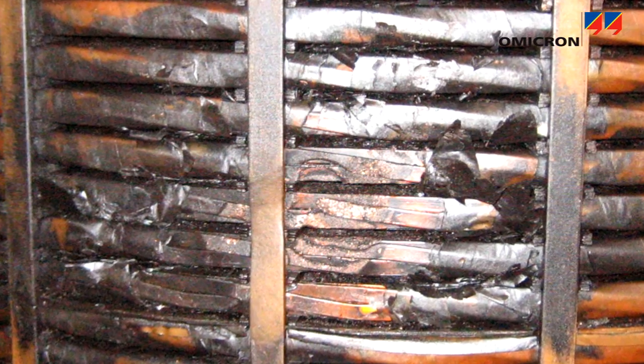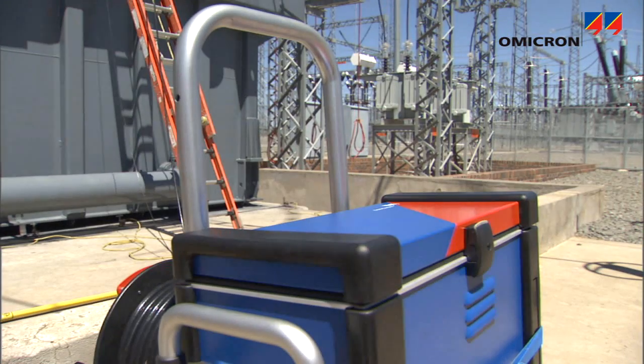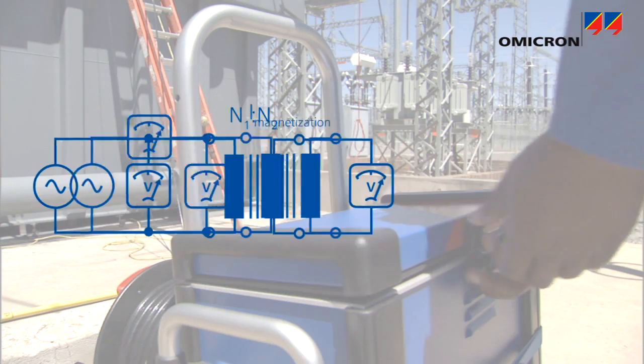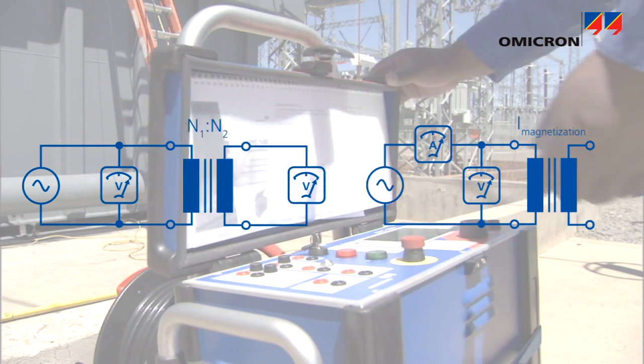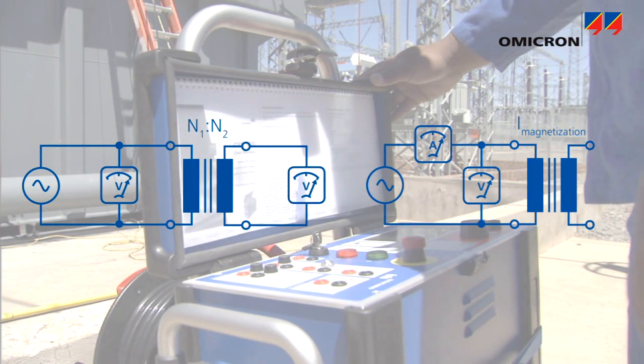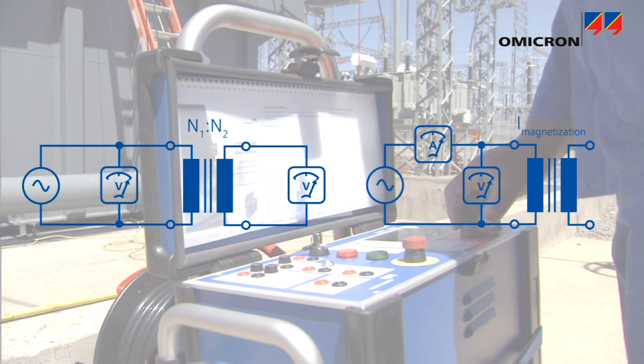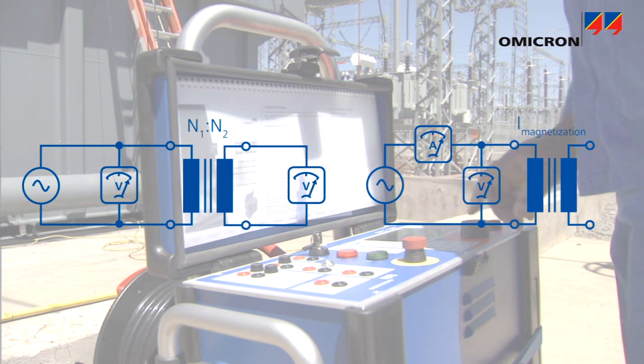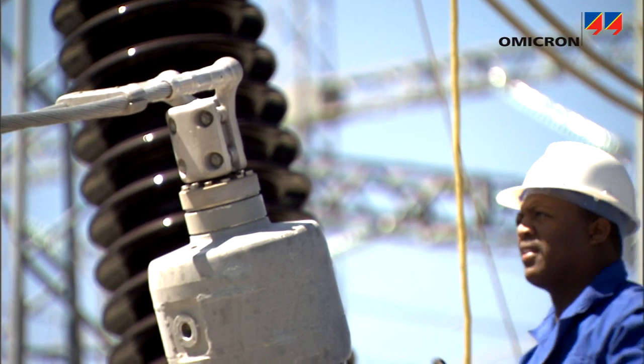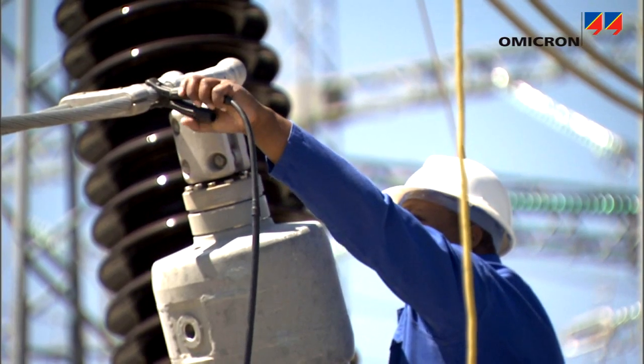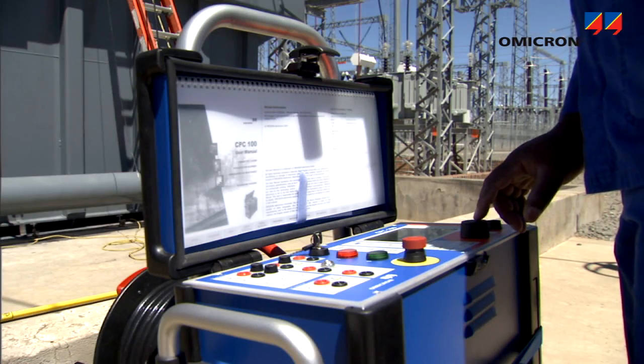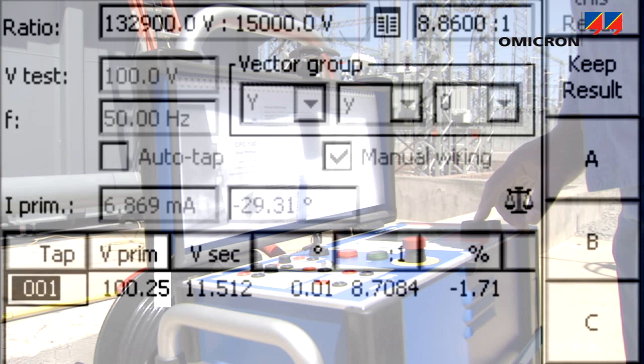With the CPC 100, the ratio and magnetization current — or excitation current — can be measured at the same time. At the transformer's primary side, high voltage is applied to one phase.